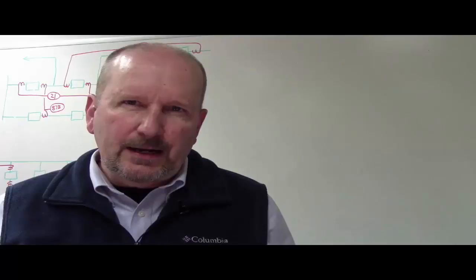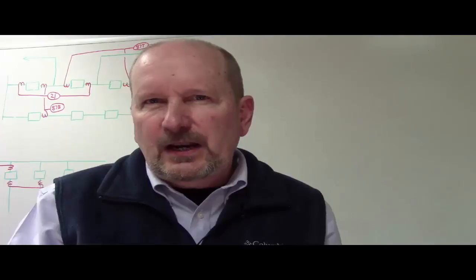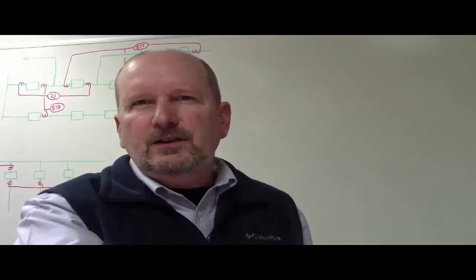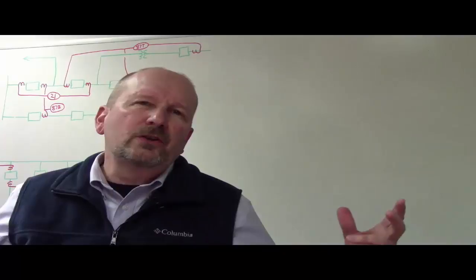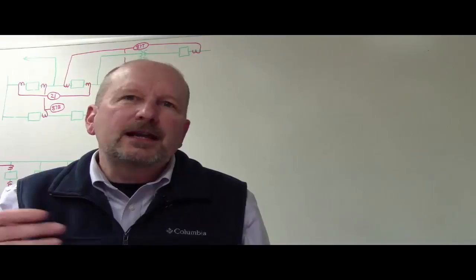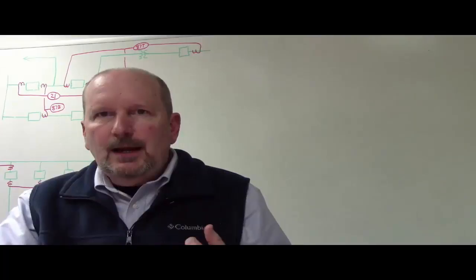If a circuit breaker is not trip free, it is not a circuit breaker. This is a fundamental reality of circuit breakers and a really important concept to have an intuitive understanding of. Now think about this in the context of a 500 kV breaker on the transmission system — a station operator closes in on a fault unknowingly and holds the control handle closed for a second or two. A second or two on the transmission system is an eternity. Within two seconds you could collapse the entire voltage of your system and lead to a regional outage.